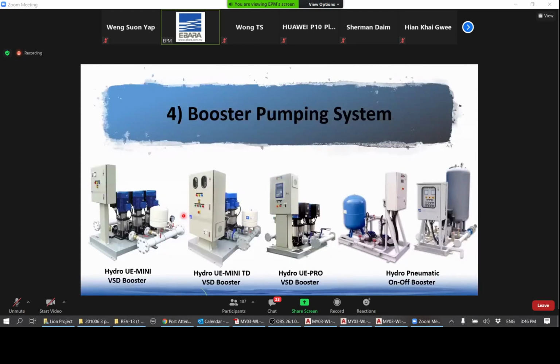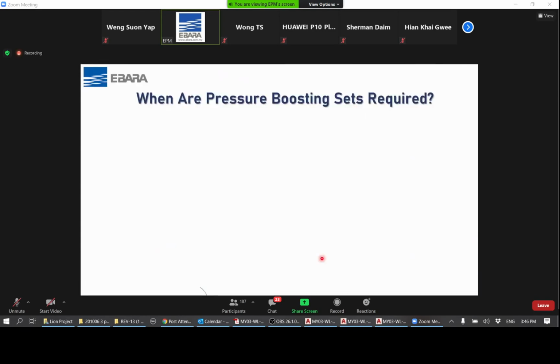The next pump we are going to talk about is what we call booster pumping systems. A booster pumping system is not a single pump, but is known more as a package booster set, like what you can see from the pictures here. Many consultants or building owners just call it booster pumps in the building, but essentially it is made up of a system of a few pumps, a dedicated control panel for those pumps, and either a large pneumatic tank or a small pneumatic tank like this, and a pressure sensing device. All these are mounted on a base frame with its pipework.